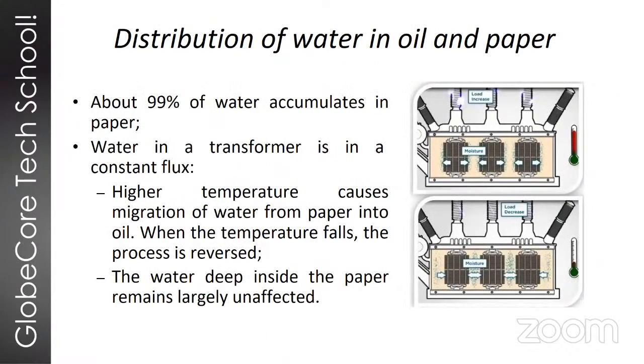So in general case, it's safe to assume that about 99% of water in the transformer is contained in its paper. However, water is never stationary and never static in the transformer. It's in a state of constant flux. When the temperature increases, the water migrates from paper into oil. When the temperature is reduced, the process is reversed and water goes back into the paper. But it's also important to keep in mind that the water deep inside the paper, in the layers of paper, largely remains unaffected. So this is another thing to consider. Next slide, please.